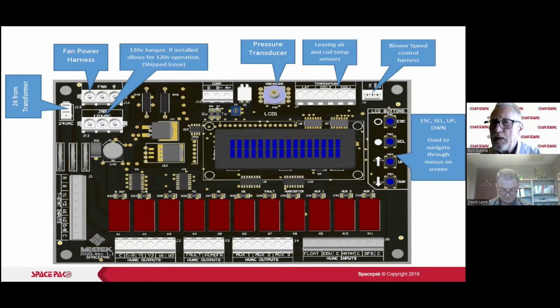Blower coil, blower speed control harness. Okay, that's where the motor head hooks up to by the wiring harness. That's where the volt DC signal is sent to the motor head to tell it how many times it has to turn per minute. The LCD buttons are below. That's where the setup is. There's a link in the handouts. There's a sheet that has a couple of links, but you can just Google it.